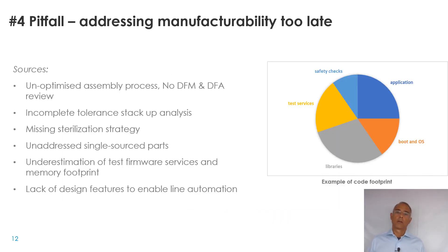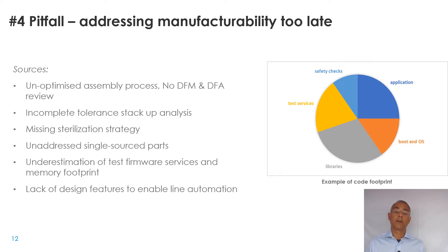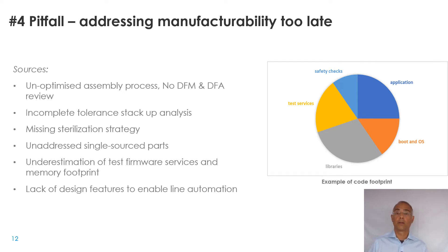Pitfall number four: addressing manufacturing requirements too late. From the earliest days of design, you need to focus on how the device will be assembled — ideally in an automated way — how it will be tested and calibrated given the small form factor, and the sterilization strategy, which may exclude certain methods due to the presence of electronics. You also need to plan for all the software needed to calibrate and operate the device in the factory, which can absorb up to one third of the entire memory footprint and may require adopting a more expensive silicon with wider memory.